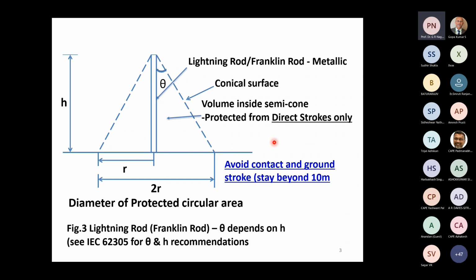The lightning directly hits the rod tip, and therefore it will not hit this area, this area at the ground level. So this is a protection from direct strokes. As we will see a little later, other dangers like contact and ground current potentials can be very substantial. That's very dangerous, but is really worth repeating. Lightning rods of this kind, this particular pole, protect against direct strokes. It attracts the lightning to itself, then conveys it to ground through the down conductor system and the earthing system.